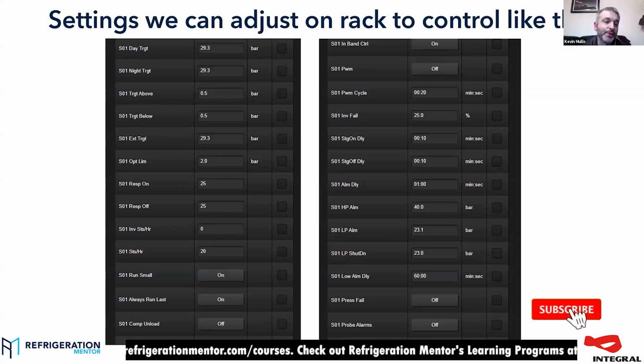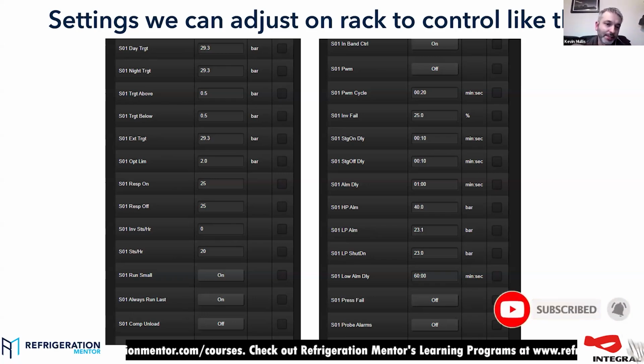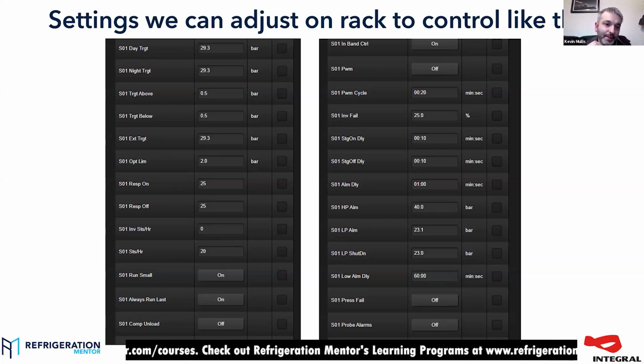And my response time, you can go up to 60 on the response time for your compressors, is 25. So that's reasonably quick, but not crazy quick. And so we've got, it's just on the second tab, we've got in-band control on. So in-band control on RDM means that when you're within that half a bar above and half a bar below, but not exactly on your set point, it will move the inverter or the variable capacity compressor, whatever you've got, to try and achieve it. But until you drop out of the plus 0.5 or minus 0.5, it won't bring another compressor on.